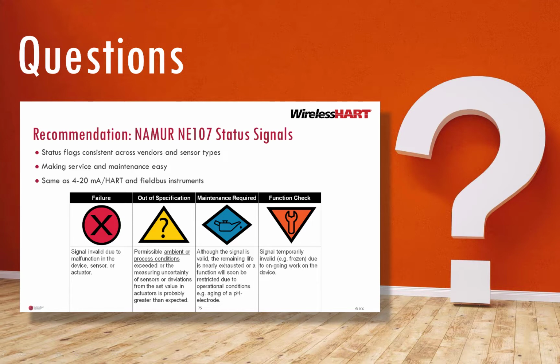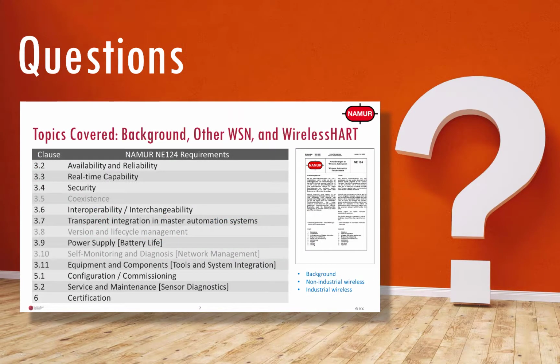And these standard signals are used for all kinds of instruments. It doesn't matter if it's WirelessHART, 4 to 20 milliamp HART, Foundation Fieldbus or even Profibus. All of them use the same 4 signals, for consistency, so it becomes very easy to use. However, all of the other requirements that I spoke about today, let me go back to this slide, about 14 requirements, are very specific to wireless. That's what goes into the NE124 recommendation. So that's the difference.